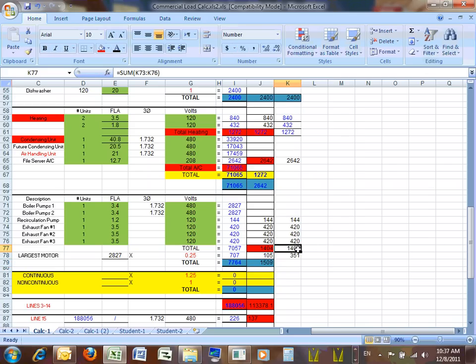Did I include the one at the bottom with it? No, I don't want the maximum of the sum, though, the maximum of the top ones. There you go, right here. I took the maximum, guys, look at this. I took the maximum of these four loads and add 25% on it.